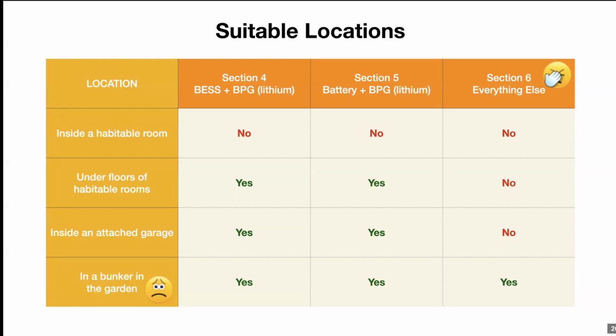Section 5 is where you have a pre-assembled lithium battery system that you connect to PCE, connect to an inverter or a charge controller. So that would be where you've got, say, an LG Chem battery or similar, which meets the compliance of the best practice guide requirements, and you connect PCE to it. And the reason why it's got a few more clauses is that you are doing some on-site manufacture now, which is you're selecting the cables that go between the battery and the PCE, you're selecting the protection for those cables, the location of them, etc.